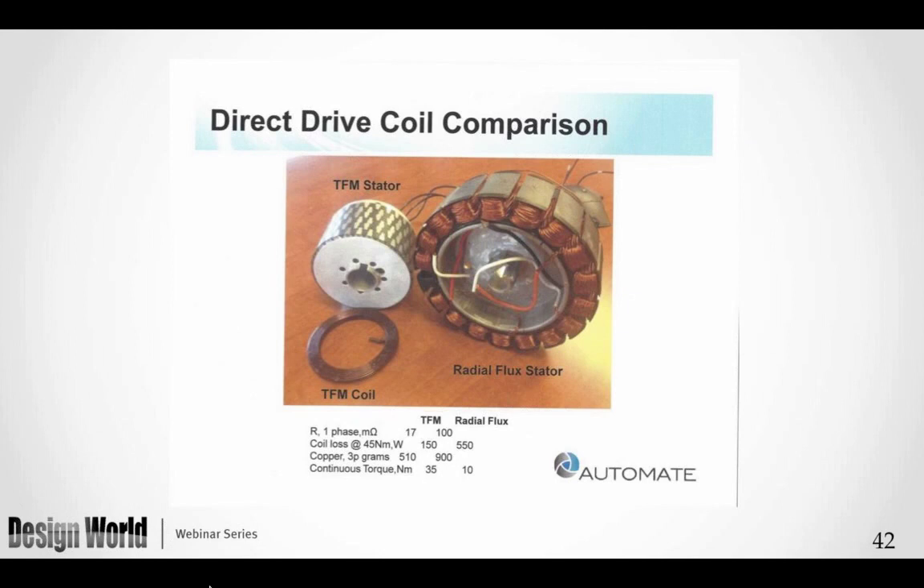Looking at the coil comparison: buried inside the TFM stator are a number of TFM coils. The conventional motor on the right uses a segmented stator approach with coils around each tooth independently. Key differences: resistance is much lower — 17 milliohms versus 100 milliohms comparing transverse flux to radial flux; coil losses are about one-third at the same torque level; copper used is about half; and continuous torque is three and a half times greater.